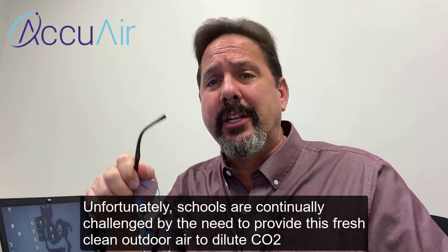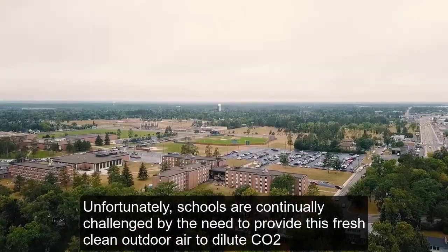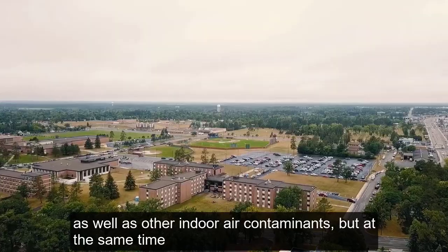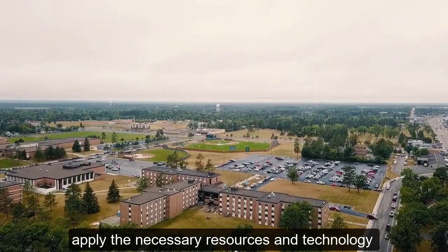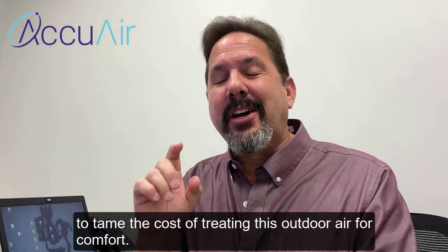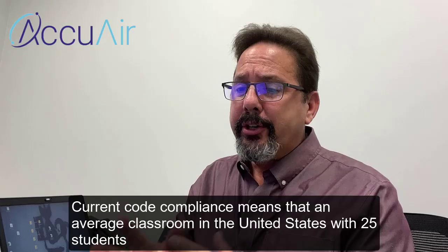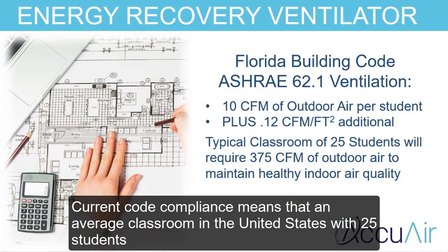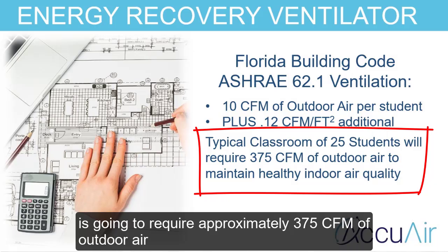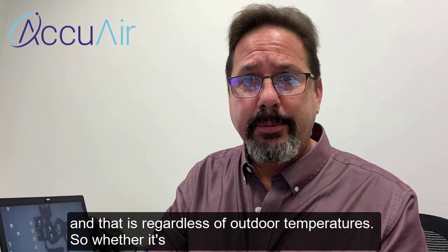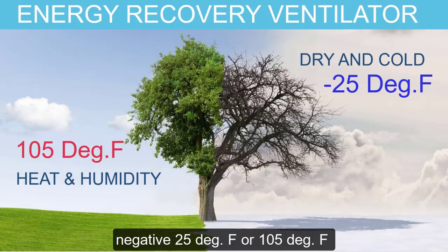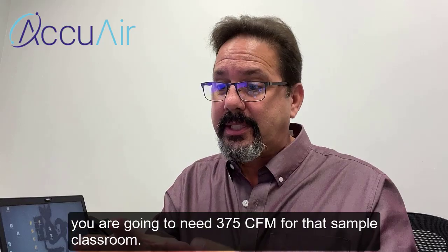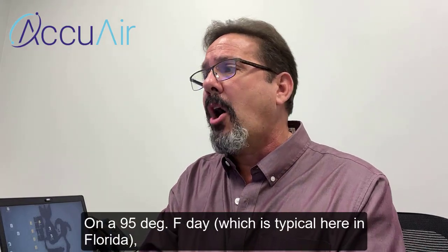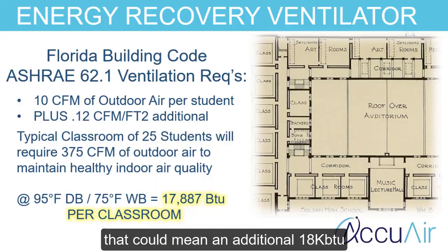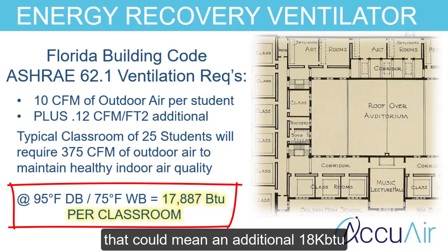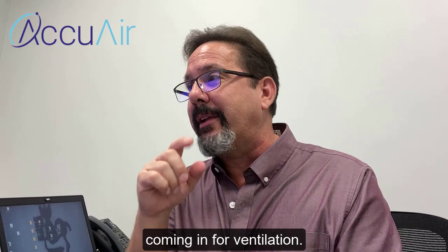Unfortunately, schools are continually challenged by the need to provide this fresh, clean outdoor air to dilute CO2 as well as other indoor air contaminants, but at the same time applying the necessary resources and technology to tame the cost of treating this outdoor air for comfort. So current code compliance means that an average classroom in the United States with 25 students is going to require approximately 375 CFM of outdoor air. And that's regardless of outdoor temperature. So whether it's negative 25 degrees Fahrenheit or 105 degrees Fahrenheit, you're going to need 375 CFM for that sample classroom. On a 95-degree day, which is typical here in Florida, that could mean an additional 18,000 BTUs just to treat that outdoor air coming in for ventilation.